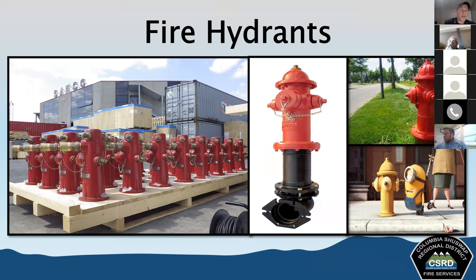Hydrants can fail. Failures or reductions in water supply or pressure can result from any number of things. It could be from a damaged hydrant where the valves or the connections are damaged, a broken water main, greater demand happening than the system can provide for, and that's a very common occurrence in our area.